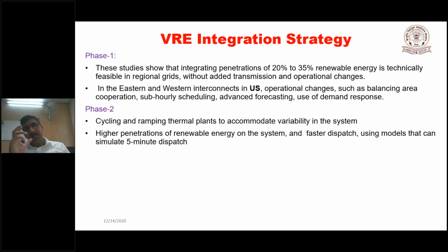One more thing: this economic load dispatch, 1 day ahead, works for a 15 minute interval. So the plan I cited here is for 12:30 to 12:45. It is assumed that within a 15 minute interval, the variation in load is not so much. There may be some variation, but that can easily be offset with the help of primary and secondary control of the governor. But when you have more renewable in the system, if the portion of renewable is more than 50%, then it is not only the load side where you get error, you will get error from the generation side itself, because you can't estimate the exact amount of generation at tomorrow's 12:30.